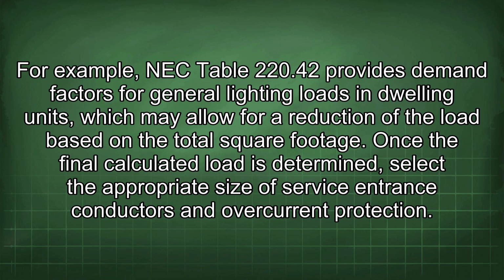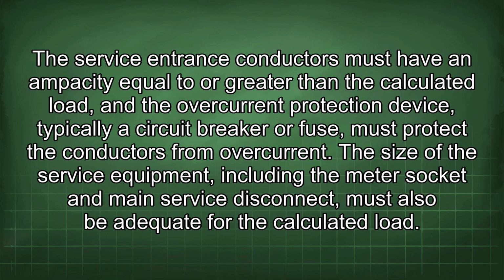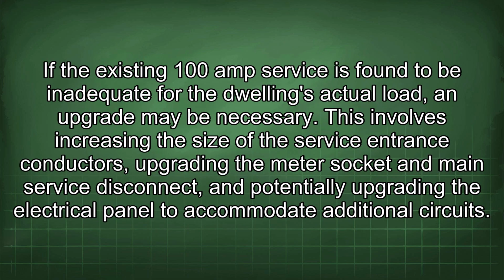Once the final calculated load is determined, select the appropriate size of service entrance conductors and overcurrent protection. The service entrance conductors must have an ampacity equal to or greater than the calculated load, and the overcurrent protection device, typically a circuit breaker or fuse, must protect the conductors from overcurrent. The size of the service equipment, including the meter socket and main service disconnect, must also be adequate for the calculated load. If the existing 100 amp service is found to be inadequate for the dwelling's actual load, an upgrade may be necessary. This involves increasing the size of the service entrance conductors, upgrading the meter socket and main service disconnect, and potentially upgrading the electrical panel to accommodate additional circuits.